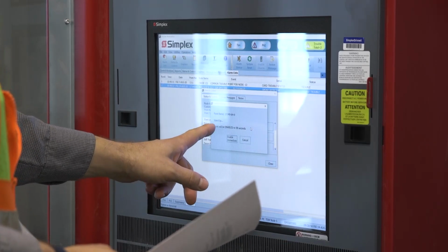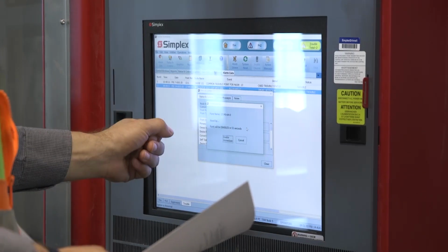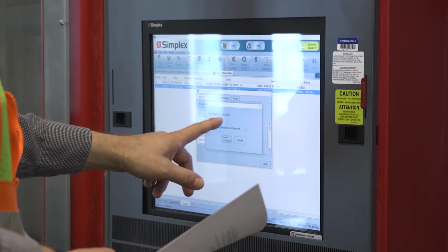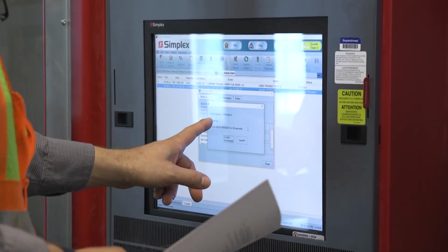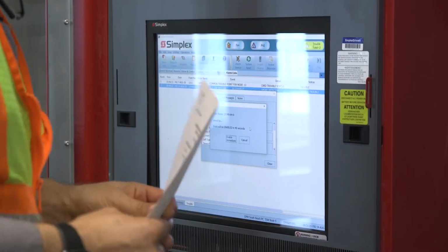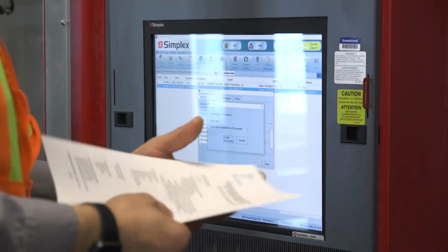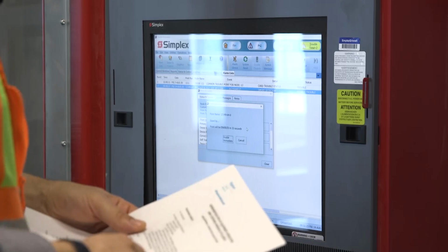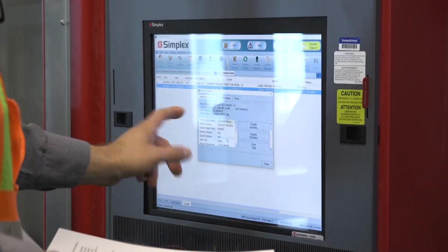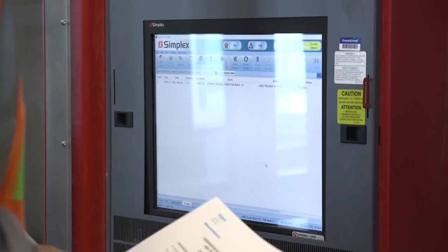And it gives you a time, like 1 minute. The point will be enabled in 1 minute. It's a delay. But if it's going to go into alarm, it says will alarm. For example, if the smoke detector is still in alarm with a lot of smoke, it's going to say will alarm. So you press cancel. You don't want to enable because it's going to go into alarm. This one says will be enabled, so you can also press enable immediate. So it's already enabled.